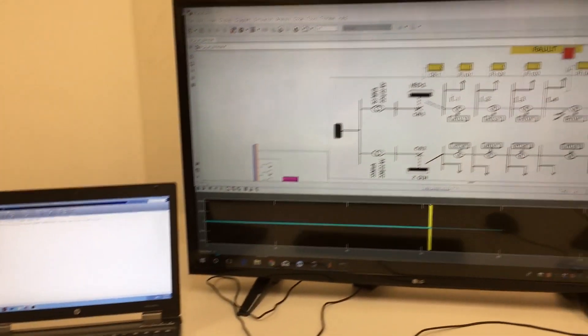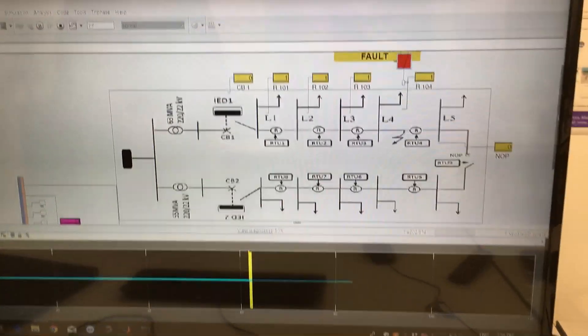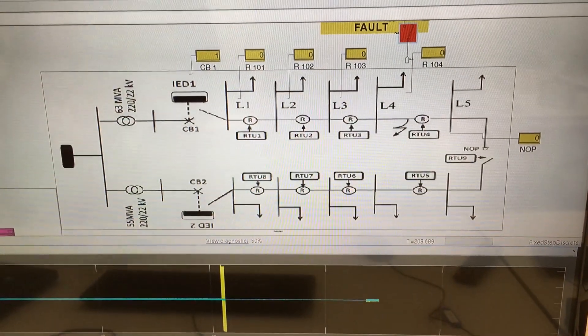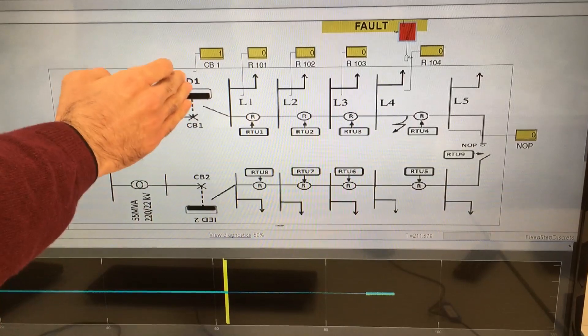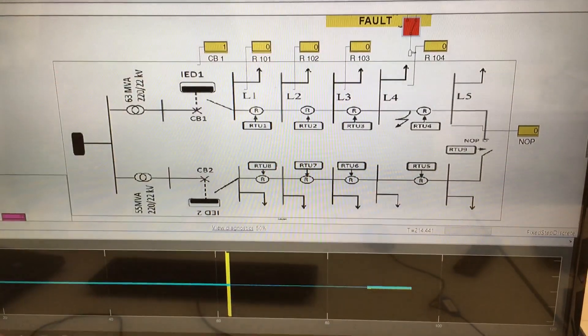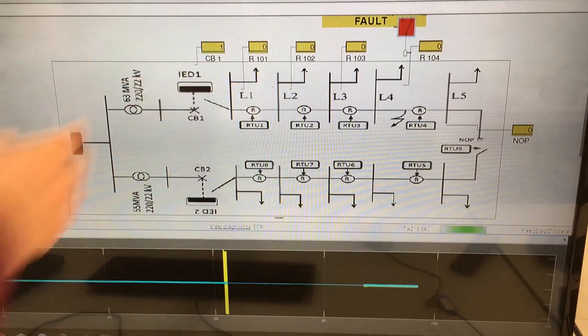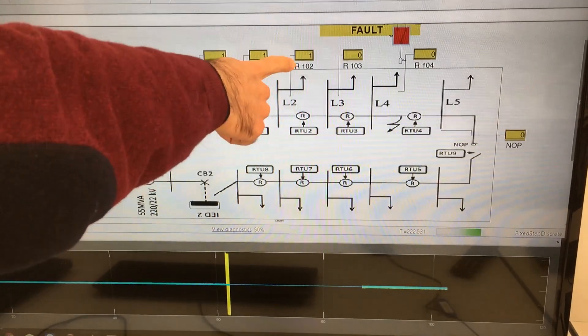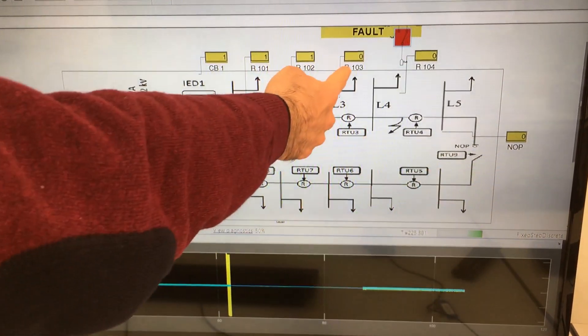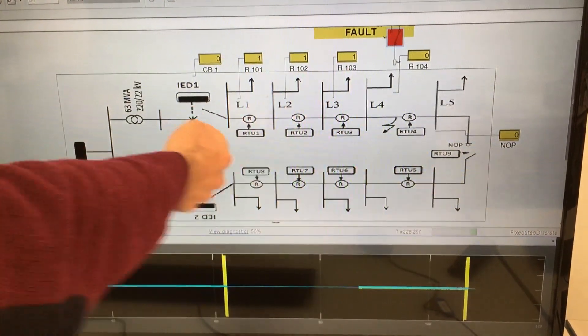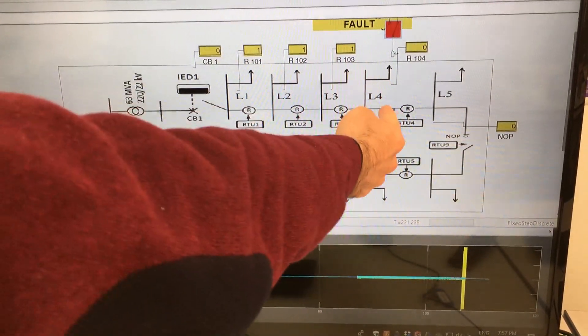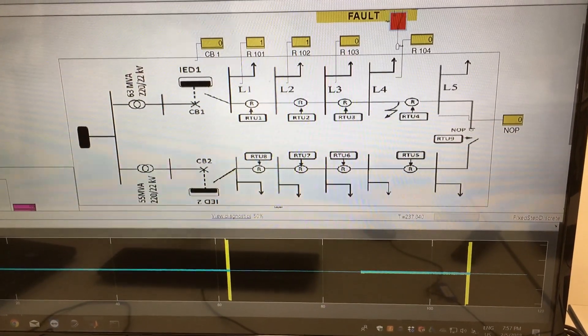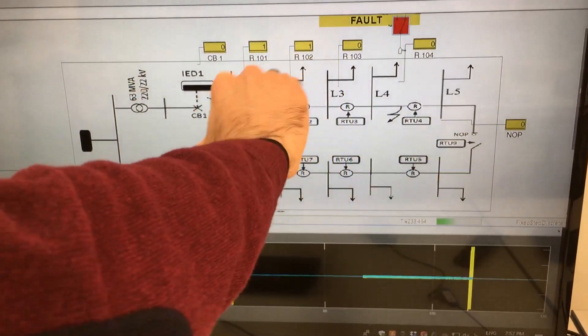We intentionally impose some delays into our communication architecture to be able to follow. Then FDIR sends commands to open all the reclosers in the feeder, then sends commands to the circuit breaker to close it back, and starting from the upstream recloser, it sends commands to close the reclosers one by one. Recloser number one is closed, now recloser number two is closed. And once recloser number three is being attempted to close, the circuit breaker status is zero, because the fault is after this recloser — so we confirm the fault is after this recloser.